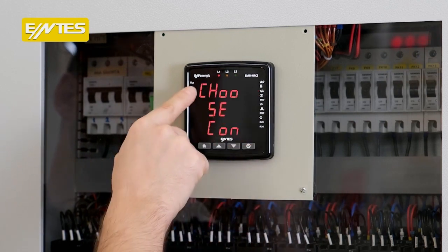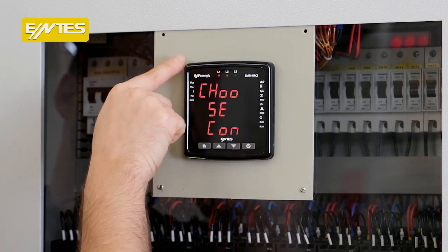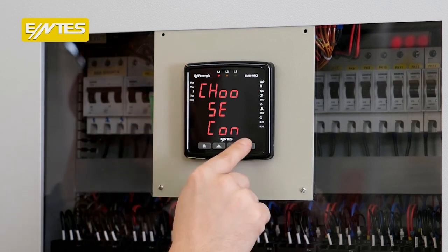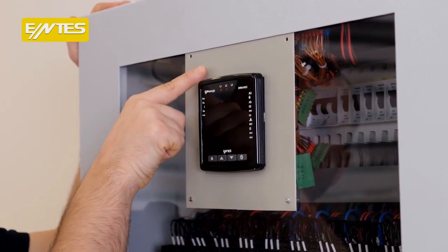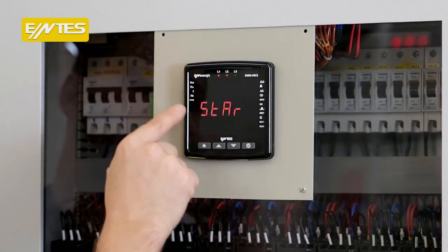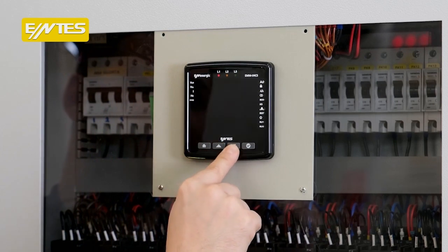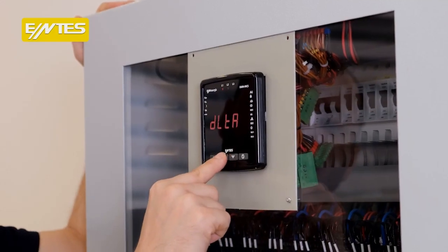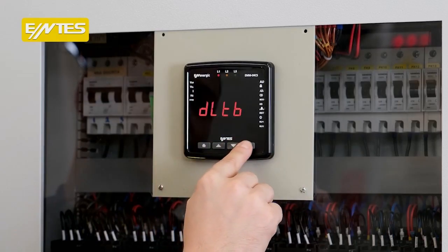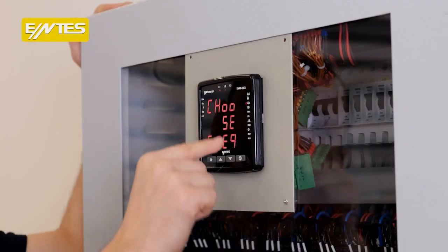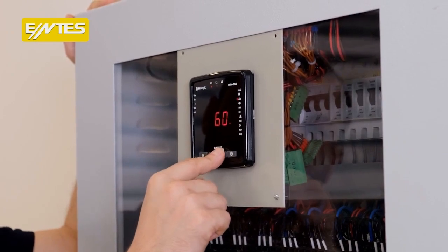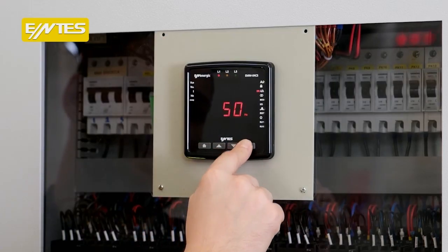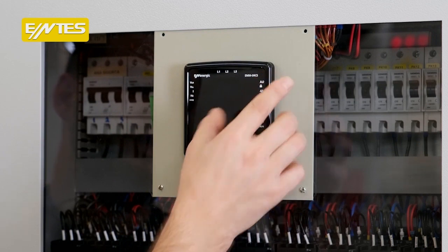They want us to explain how we connect the kind of connection at the measurement input on the rear of the device. Look, there is a 3x4 wire here, so we tied it 3 times and tied the neutral. There are 5 types of connections in the user manual. It is entered here by selecting the appropriate one from there. We select the 3-phase 4-wire connection. We press the OK button. Select the frequency. It supports frequencies of 50 Hz and 60 Hz. We select 50 Hz. We pressed OK. The installation steps were finished like this.